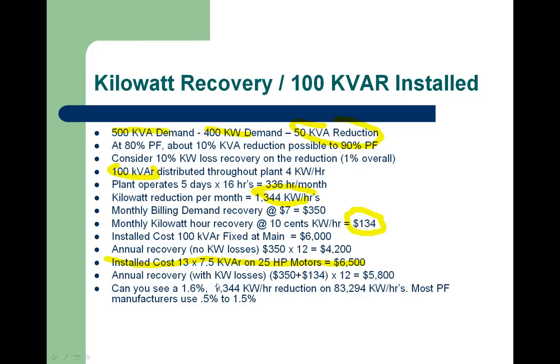So if we looked at the combination of $350 per month in demand charges plus $134 in I²R losses, we would end up with annual savings of $5,800 over the $4,200 installing the capacitor banks at the main. So in this particular case, it's about a 1.6% reduction in kilowatt hours, and this was based on another site that actually used about 83,000 kilowatt hours. So it's about a 1.6% reduction in kilowatt hours.